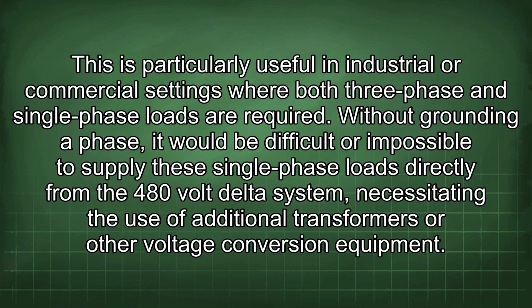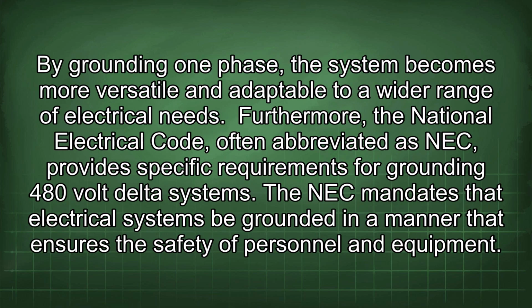This is particularly useful in industrial or commercial settings where both three-phase and single-phase loads are required. Without grounding a phase, it would be difficult or impossible to supply these single-phase loads directly from the 480-volt delta system, necessitating the use of additional transformers or other voltage conversion equipment. By grounding one phase, the system becomes more versatile and adaptable to a wider range of electrical needs.